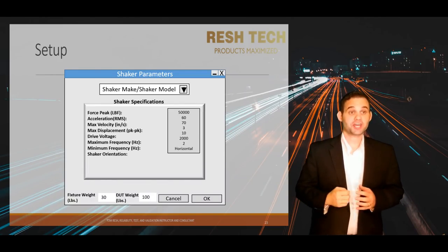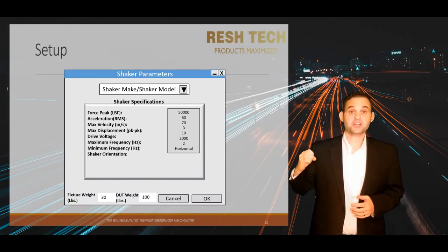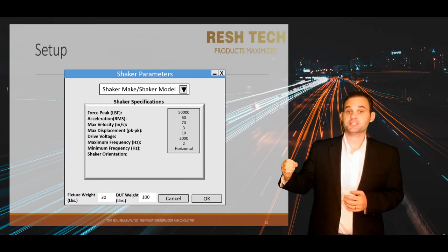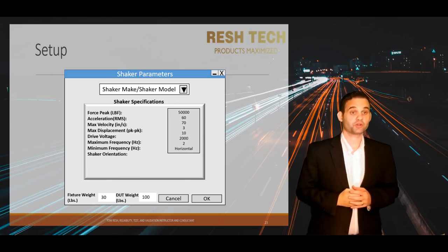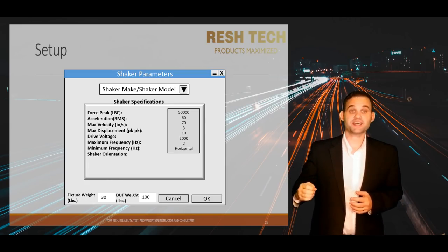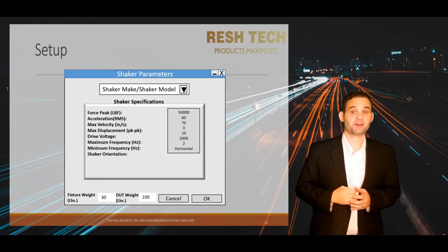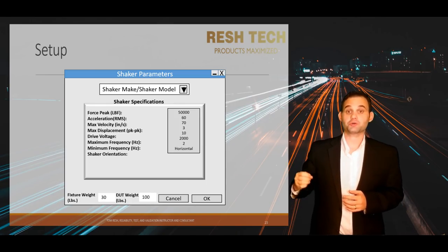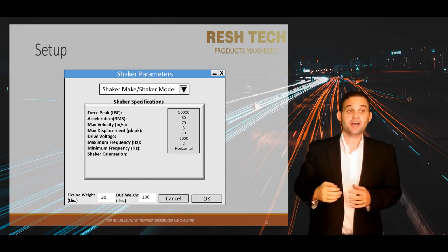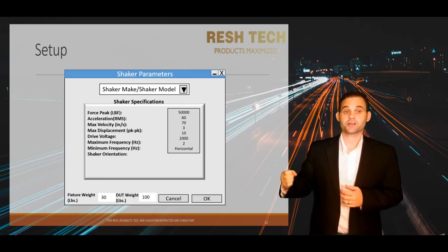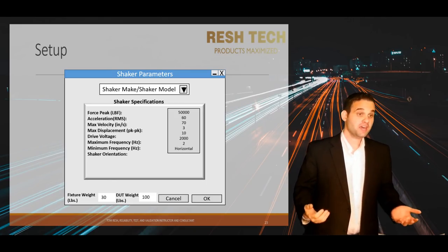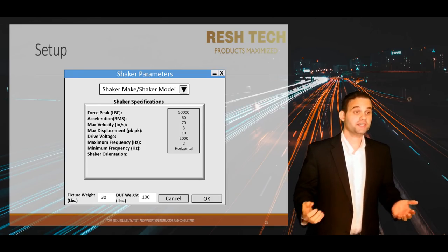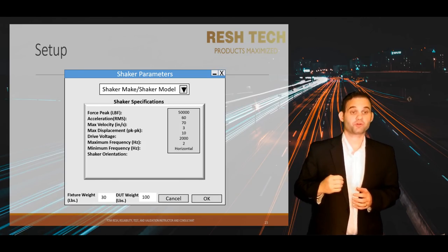Let's take a look at shaker parameters. The shaker parameter menu is where you configure the limits for your vibration test system. Many controllers have preset limits for various types of vibration test systems — it is as simple as selecting your shaker make and model and selecting vertical or horizontal configuration. If your shaker is not a preset in the controller, you will need to enter the parameters manually.